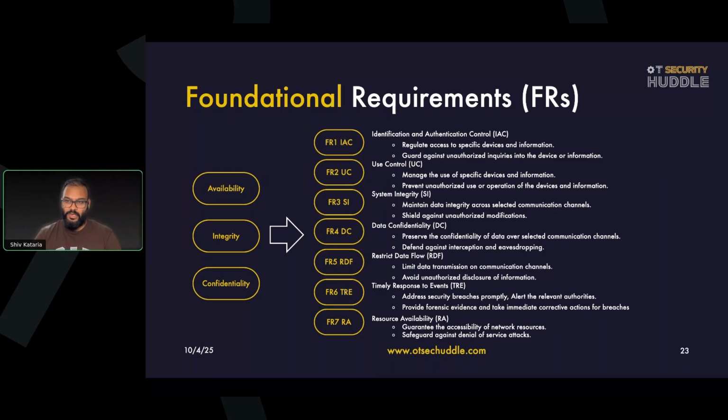If you really have a requirement of sharing some data going from your OT to IT, implement a data diode. Do you need something coming in from IT to OT? Put some broker service in between and use that broker service. Don't directly give access to the OT environment, because your IT services are the ones which will get impacted first whenever an attack happens, and then they might pivot towards your OT environment. So you should not create any direct connectivity from your IT to OT. And for that purpose only, selectively you give access to data diodes.